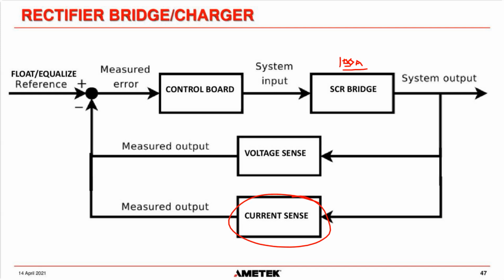Okay, so we're saying 100 amps is all that we can put out of this bridge. Then what we do is we actually have a current shunt on the output of the system that measures the current, and that reports back to this current sense circuit here. So if we go above 100 amps, then the current circuit says, okay, we've got too much current, and it puts out an error signal and says, we need to tell the control board to phase back the SCRs. In other words, turn the SCRs on later in the cycle. In other words, reduce the output voltage, because the only way we can reduce current is to reduce the voltage of the charger. That is the only thing we have control over.